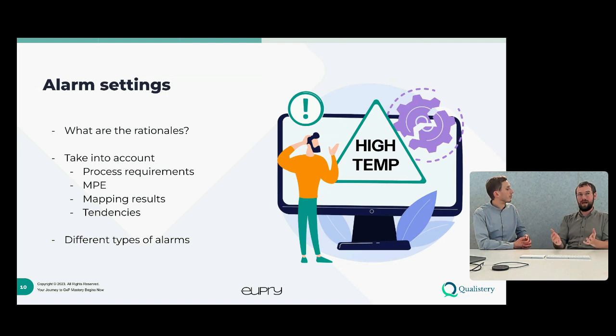Lastly, in terms of alarm settings, also consider tendencies. If you set a data logger at your cold spot, but temperatures are generally rising due to aging equipment, that's fairly normal. Are you still within the hotspot? Are you still within the settings? All those different things really have to come into one place, and they have to be documented. Otherwise, it's sort of meaningless.